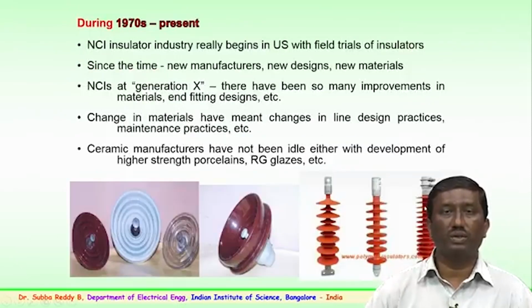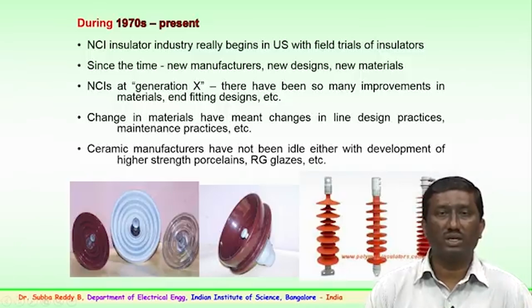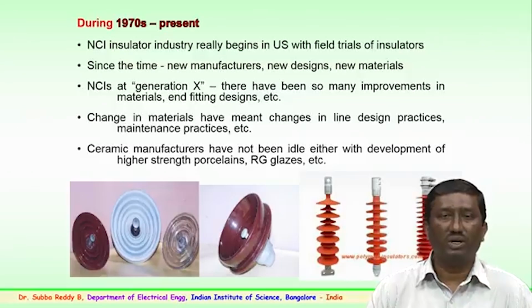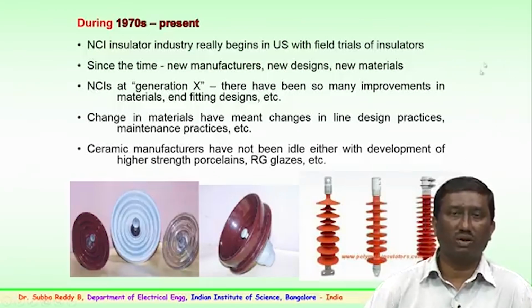So, during the 70s to the present, the non-ceramic insulator industry really began, with much better information and much better field trials of the insulator. Since then, new manufacturers, new designs and new materials were incorporated, and new types of fillers were introduced into the compounds, wherein the non-ceramic insulators of the present, third generation, are available with various types of filler materials embedded into the silicone rubber. Parallelly, when the technology grew for polymer or silicone rubber, the ceramic manufacturers have also not been idle. They also tried to improve by using high strength porcelain, resistive glazes and coatings on the insulator surfaces, and so on, to sustain the technologies for the transmission system.